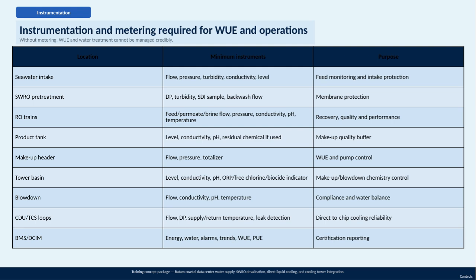For example, at the seawater intake, instruments like flow, pressure, turbidity, conductivity, and level sensors are critical to monitor the feed water and protect the intake system. Moving to the SWRO pretreatment stage, differential pressure, turbidity, SDI sample, and backwash flow measurements are vital to protect the membranes. In the RO trains, monitoring feed, permeate, and brine flow, along with pressure, conductivity, pH, and temperature, helps ensure recovery rates, water quality, and system performance are maintained. For product tanks, level, conductivity, pH, and residual chemical measurements ensure the water quality remains within acceptable limits.